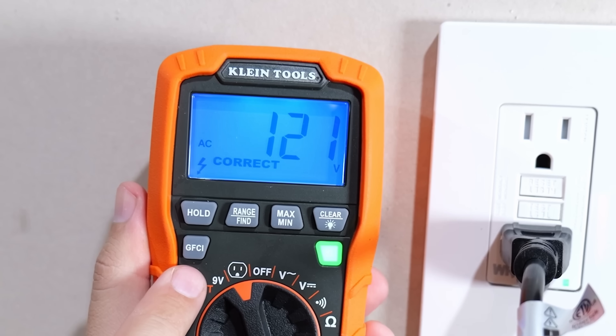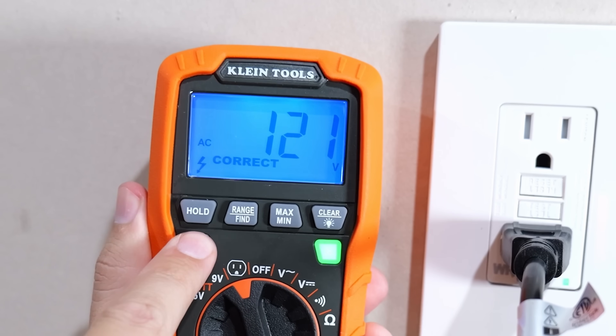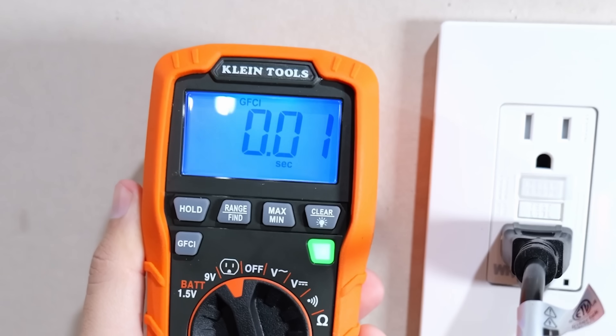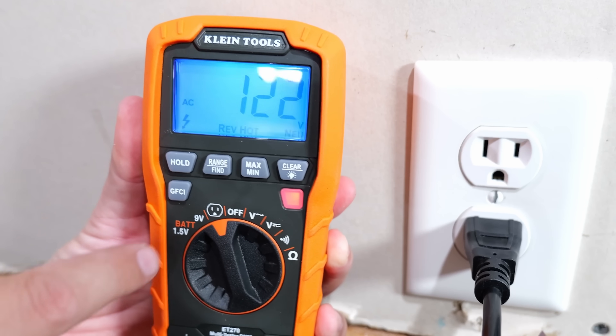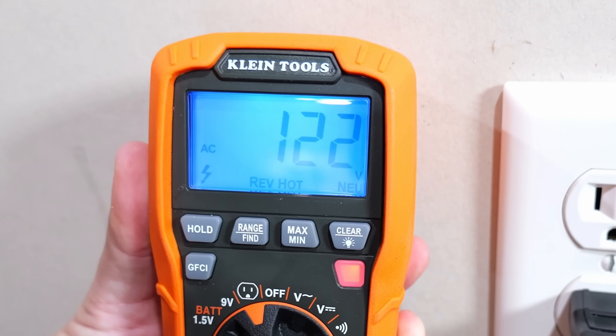Like the others, we've got our GFCI test button here. When we push it to simulate a ground fault, it was at 121 volts and again showing 0.01 seconds response time. When we plug it into the receptacle with the bad wiring, the light goes red, it beeps to alert us of an issue, and down at the bottom it shows "hot neutral reverse" — all the information you need is right there on screen.